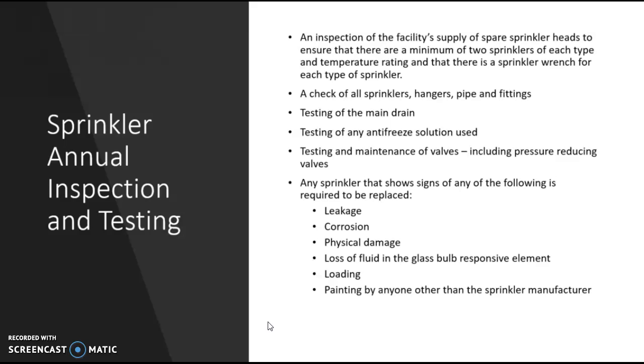We want to test the main drain, testing any antifreeze solution, testing and maintenance of valves, including pressure reducing valves, and then any sprinkler that shows signs of any of the following needs to be replaced, right? So we've got the leakage, corrosion, physical damage, anything that we know that is going to be a problem. And then we want to make sure that if it's painted by anybody else other than the sprinkler manufacturer, it needs to be replaced. Once again, these are all your annual inspections and testing.